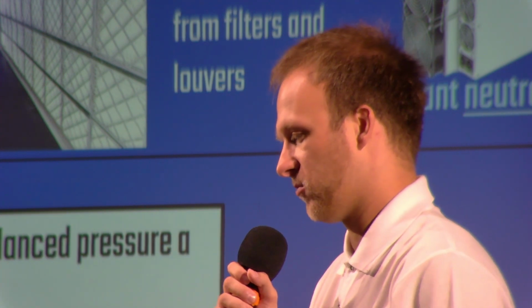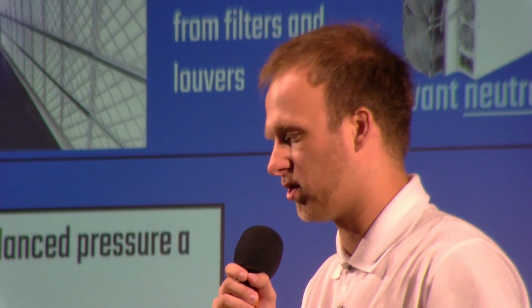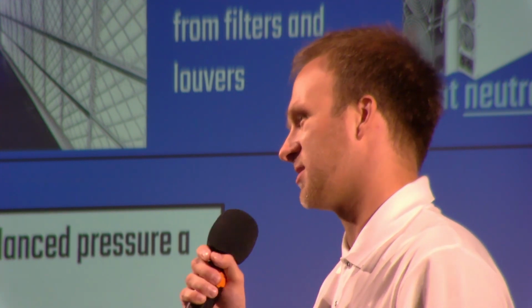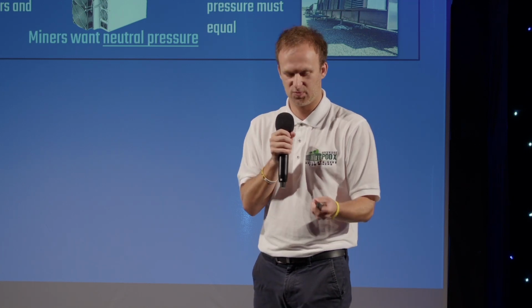Now, you might ask yourself, what happens if you have unbalanced pressure? What happens if it's too high or too low on either side? Why is this a bad thing? Well, like I said before, if you have high negative pressure on your intake, that can cause a lot of issues with weather and contaminants coming into your filter. It's definitely what causes snow to come in if you ever have problems with snow in your intake. It's just like a vacuum, pulling so hard and so fast that anything on the outside gets sucked right in. And like I said, it's largely responsible for the high pressure on your intake doors.